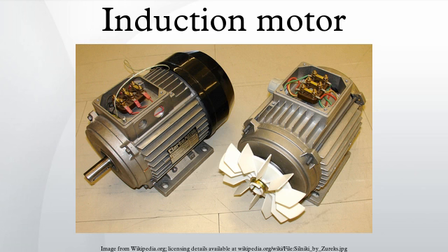Slip. Slip is defined as the difference between synchronous speed and operating speed, at the same frequency, expressed in rpm or in percent or ratio of synchronous speed. Thus, whereas stator electrical speed is synchronous, rotor mechanical speed is lower. Slip, which varies from 0 at synchronous speed and 1 when the rotor is at rest, determines the motor's torque.